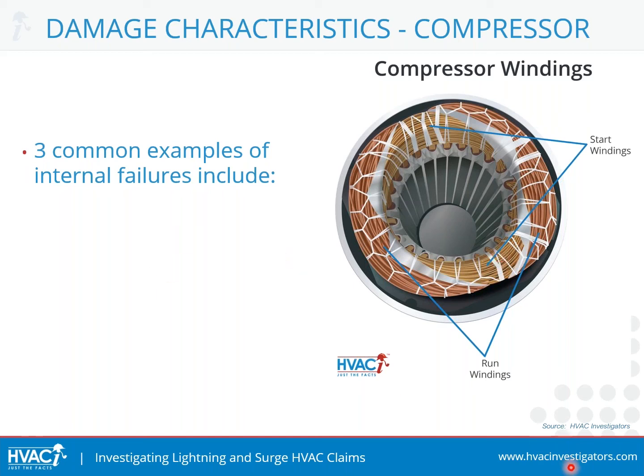The first one is winding-to-winding failure. This is the cutaway of the inside here, and these are the windings — we have the start windings and the run windings. If those windings are touching each other, which they should not be, you have an issue. If they're touching each other, you've had some sort of event going on inside to make them touch.